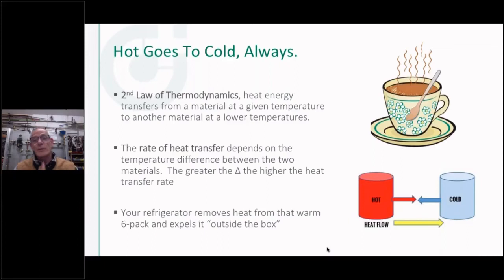So heat goes to cold, and we know that with buildings, obviously, because with the windows, the heat's going to try and go through all the low R values to the outside. And the rate of that heat transfer, how quickly that happens, or how quickly I can recover, say, an indirect tank, depends on the delta T, the temperature difference between them. So in this little example here, the hotter the temperature and the colder the temperature on the other side, the faster the transfer is going to be.